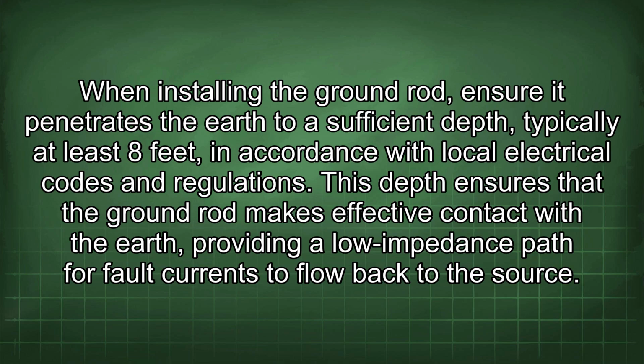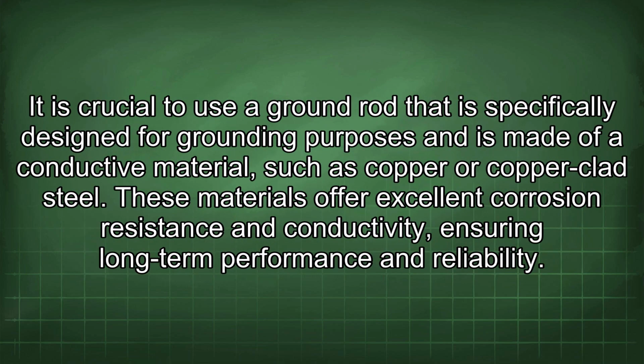This depth ensures that the ground rod makes effective contact with the earth, providing a low impedance path for fault currents to flow back to the source. It is crucial to use a ground rod that is specifically designed for grounding purposes and is made of a conductive material, such as copper or copper-clad steel. These materials offer excellent corrosion resistance and conductivity, ensuring long-term performance and reliability.